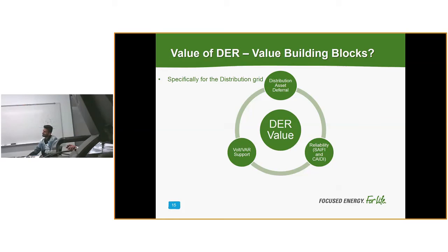Reliability is tricky because it's not technology agnostic. For distribution asset deferral and volt-VAR support, any DER can provide capacity by virtue of providing generation energy, and provide VAR - that's by definition, it provides both from an energy perspective. But from a reliability perspective, that's what we talk about specifically for outage scenarios.